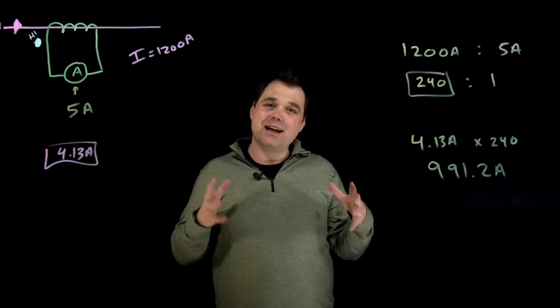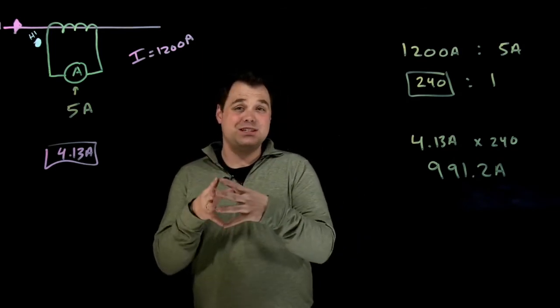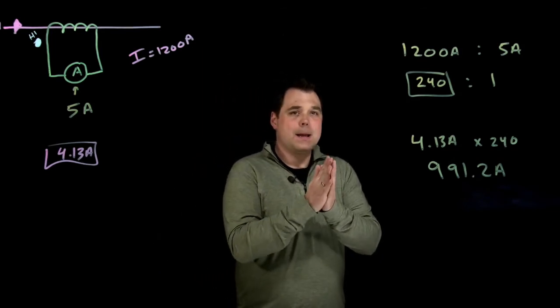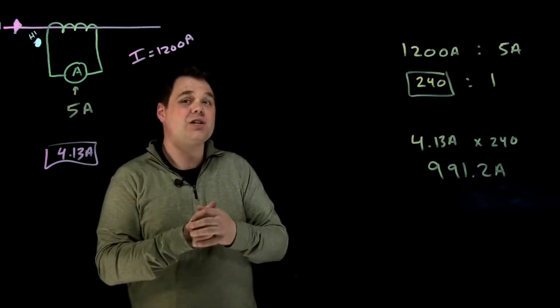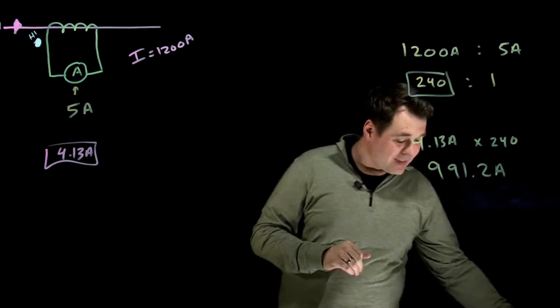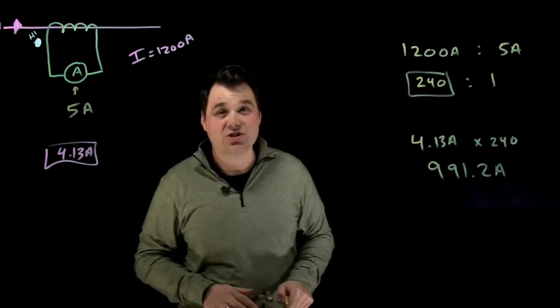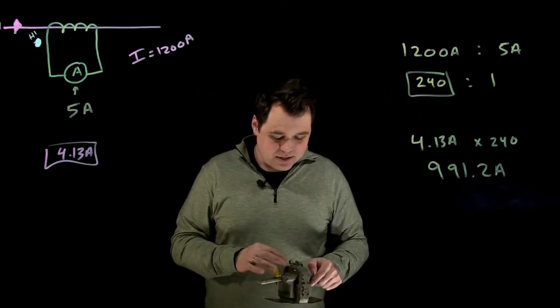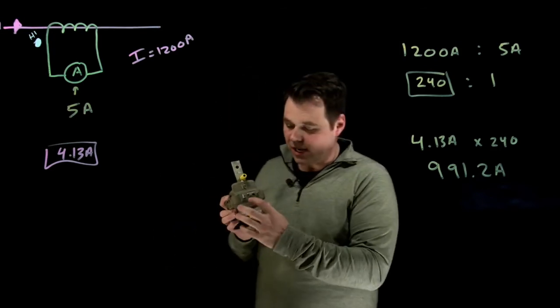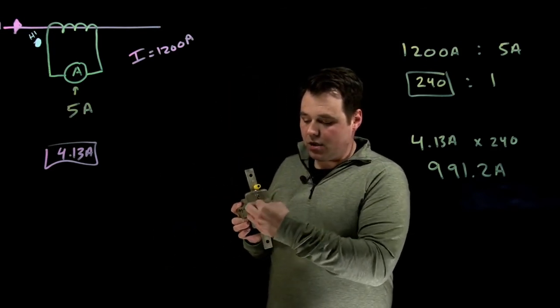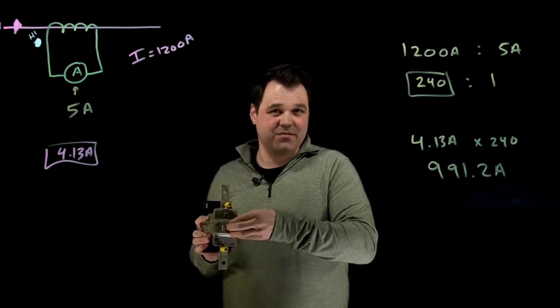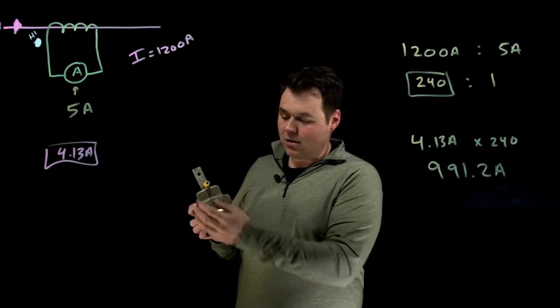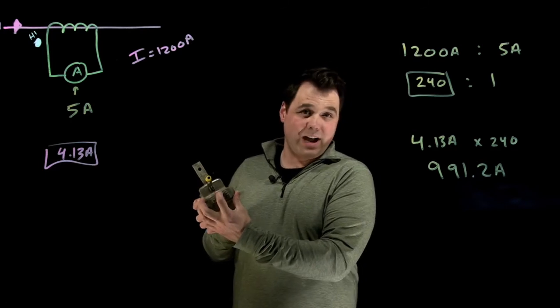But there's something that matters safety-wise with these current transformers. Because of the nature of the transformer, the super high voltage winding, it actually can never be open circuited. So what that means is on CTs, what you'll see is you'll actually see something that you can, if you have to uninstall it live or disconnect it from the circuit in any way, you can actually short it out.